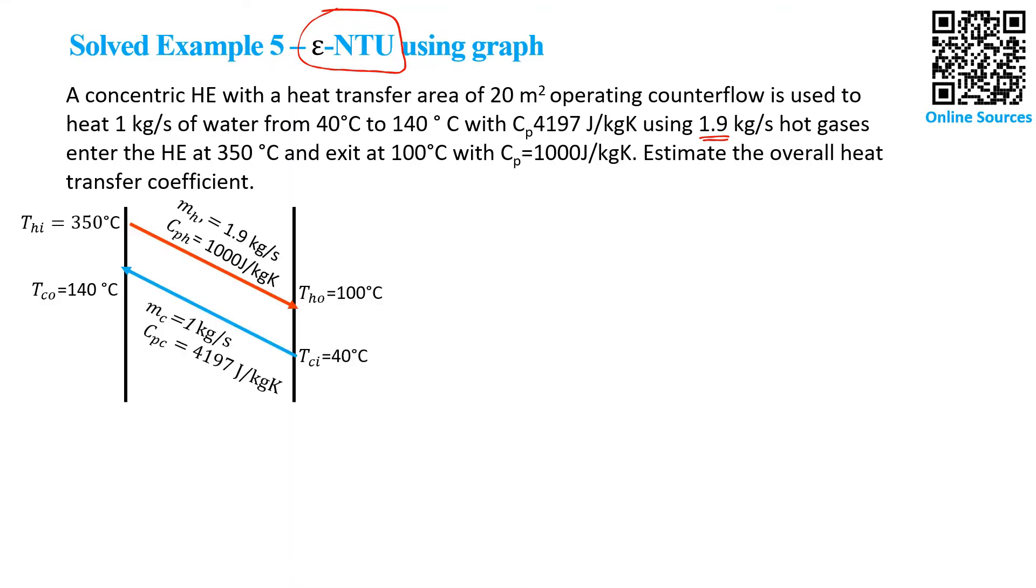I've prepared it here. From the given problem, we know that the T-hot in, this is hot gases, enters the heat exchanger at a temperature of 350°C and exits at 100°C. We are given the mass flow rate, which is 1.9 kg per second, and the Cp of the hot gas, 1 kJ per kilogram Kelvin.